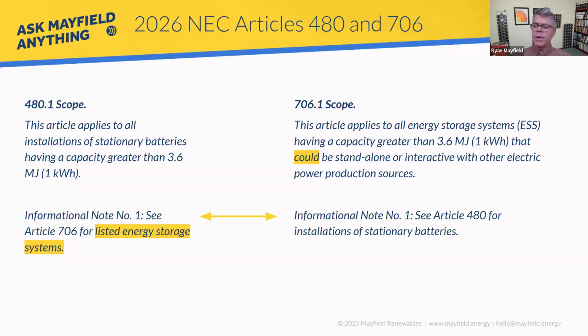Am I supposed to look at 706? The big thing is, if you see that informational note under 480, it talks about listed energy storage systems. Listed systems are those that have gone through the 9540 process and been listed. That could be a DC system, it could be an AC system, but it's a system that's been evaluated. Batteries by themselves are typically looked at under UL 1973, and that's the big differentiator.